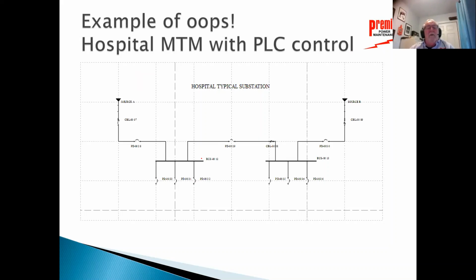There's a hospital that I do some work with, and reliability is of utmost importance. Here is a simple one line of a main distribution system inside the hospital. They have two sources, source A and source B. They even went to the point where they worked with the utility, my old utility, Indianapolis Power and Light Company, to make sure that these two sources were fed from different substations, so one substation wouldn't hurt it. Everything was PLC controlled inside this system. If we lost source A, it would open circuit breaker A and close the tie so that there would only be a momentary outage. It would recognize when it came back and go that way. All PLC controlled, very good.